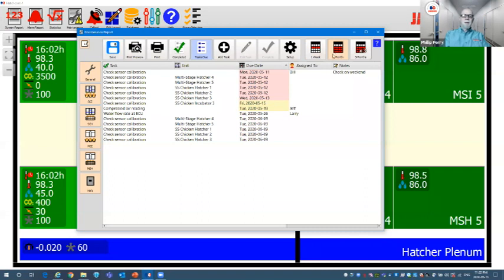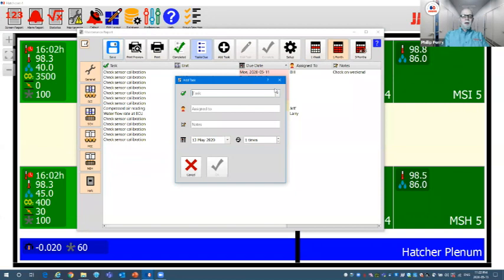If you want to see what's coming up for the next month, you can click on the 1 month, and then we see Larry here has been assigned to check the water flow rate at an ECU or check sensor calibrations or whatever. We can do these and assign notes to them. When we want to add a task, we just click on this, and have a drop-down menu. We can check off what we want checked, who we want to assign it to, type that name in. We'll say Bill, and then we can add a note if we want to, when we want to do it, how many times we want it done. So if we want to have this happen more frequently, we can change that as well and assign that.